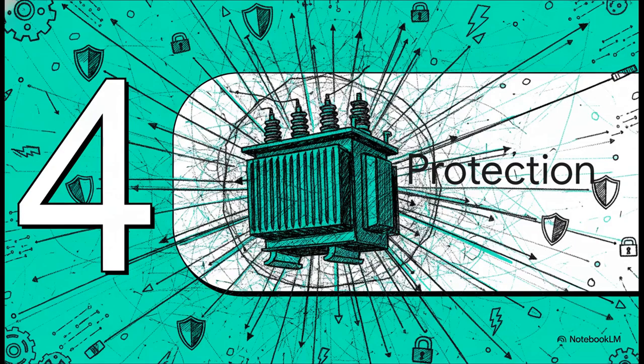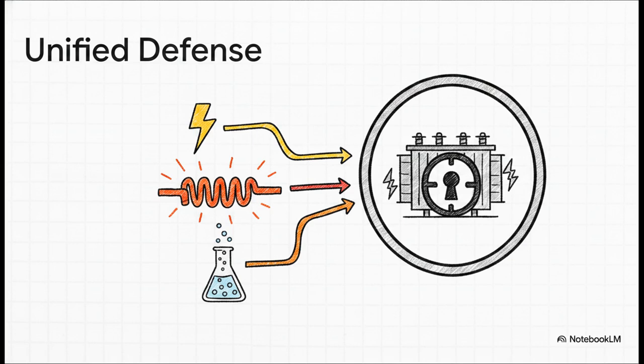Section 4. The complete protection picture. Let's look at how we bring all of this together now to show how we wrap the transformer in a truly impenetrable web of defense. Here is our unified defense strategy in action. You've got your TR2PTDF differential protection, that's your high-speed guard for sudden internal faults. Then you have your overcurrent protection, the PHLPTOC and PHHPTOC, watching for sustained external overloads. And right alongside them, seamlessly integrated via that MAP-GAPC block, is your Buchholz mechanical protection, catching those slow, invisible gas buildups. Every single one of these covers a genuinely different failure mode, but they all work together as one cohesive team, converging on a single master trip gate to save the asset.